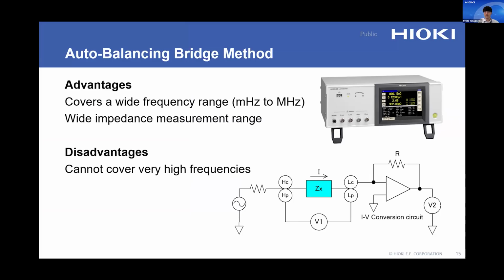The main advantages of this method are its wide frequency range and wide impedance measurement range. On the other hand, it cannot cover very high frequencies. Among our instruments using this method, the IM3536 supports the highest frequency, up to 8 MHz. So now let me briefly explain the terminals. It uses four terminals: HC, HP, LC, LP. H and L stand for high and low, and C is for current, and P is for voltage.